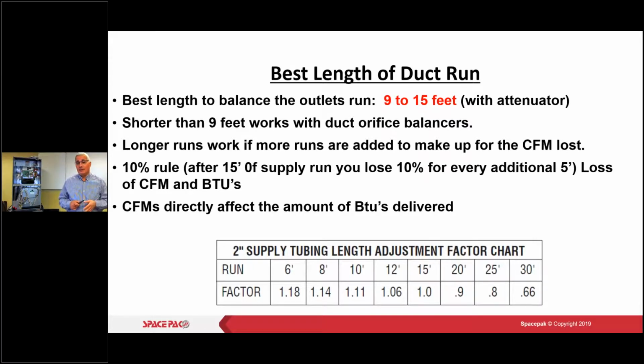It's very, very important. A lot of times we'll go out to a job where one area of the system isn't heating or cooling well. Generally, it's not cooling well. And that's because we're way too long on our 2-inch drops. The installing contractor didn't take that into account, didn't follow the 10% rule, didn't run the extra 2-inch lines to get enough CFM and BTUs out there. Any questions on this? Because this is important.